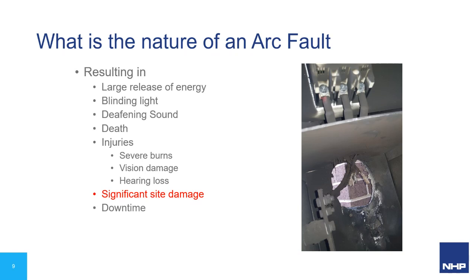And for the site as well, going away from the safety a little bit here, there's also significant site damage and downtime associated with that. If you look at the right-hand side image here, this particular arc fault completely destroyed that switchboard, and you can see the hole in the back there where it's sitting in front of the brickwork. You can imagine there's been quite a lot of damage for this to occur. Imagine the downtime for a whole switchboard to be built, manufactured, and then put in place of one that's been existing for some time.